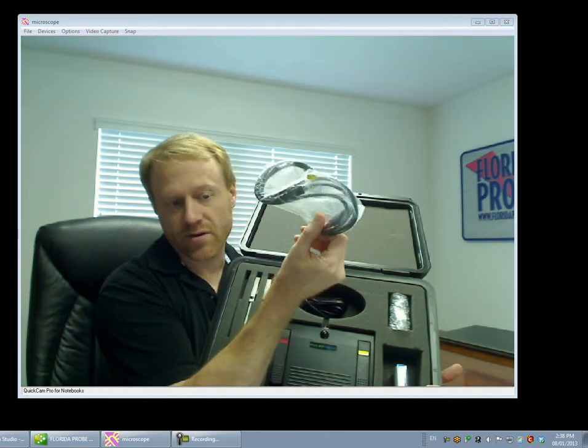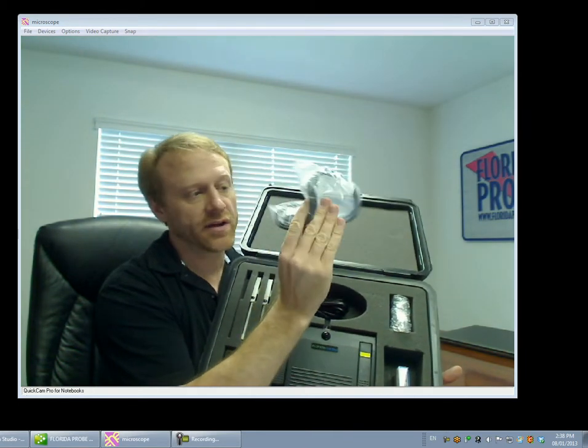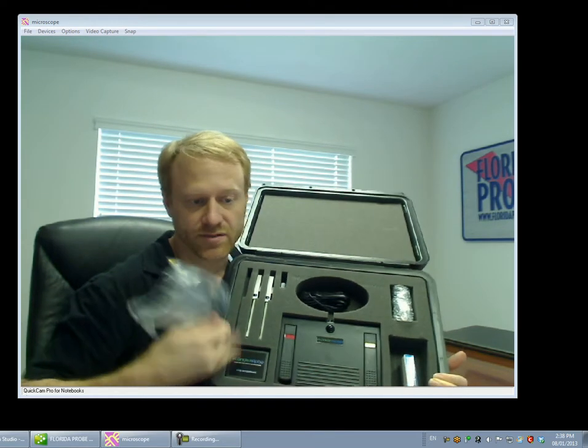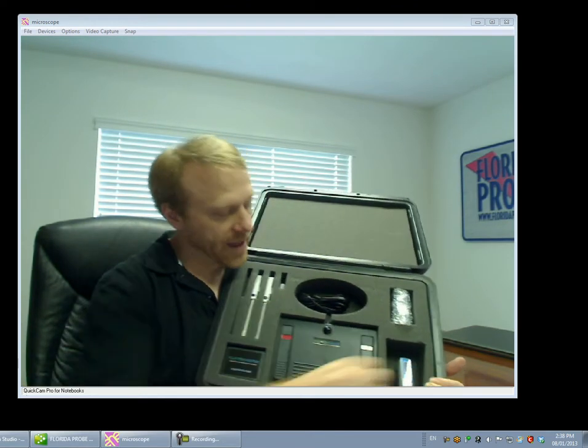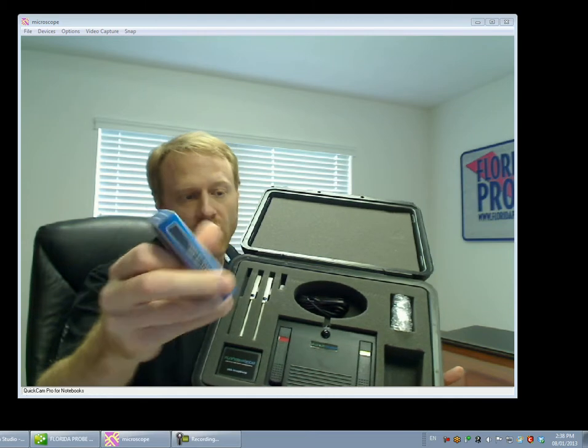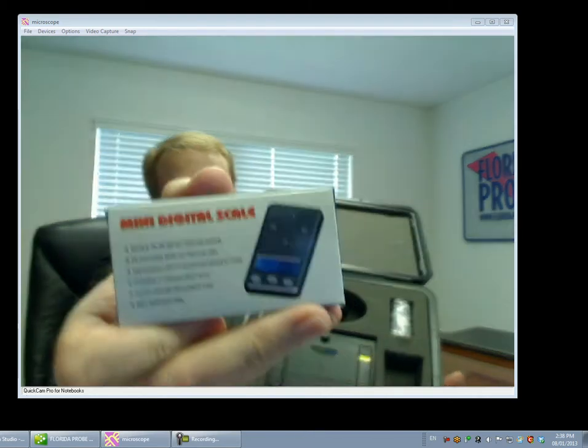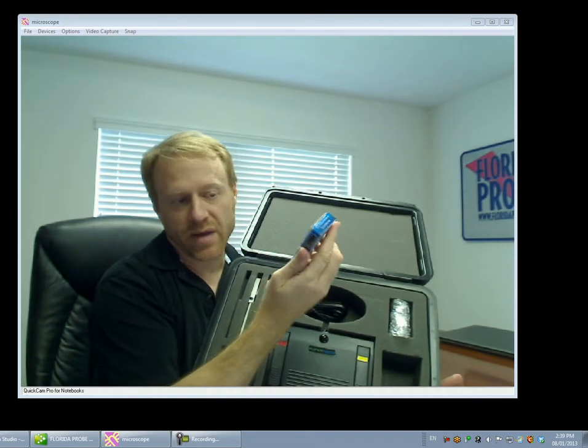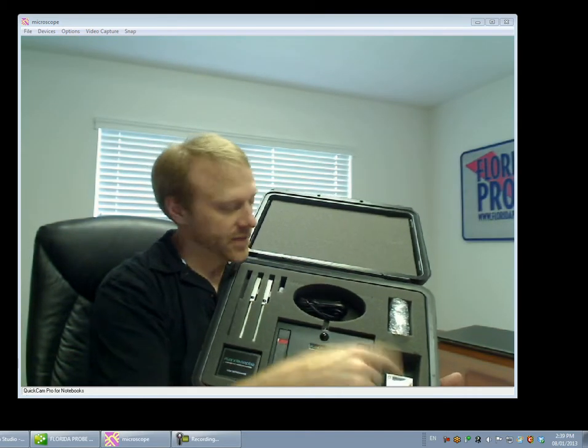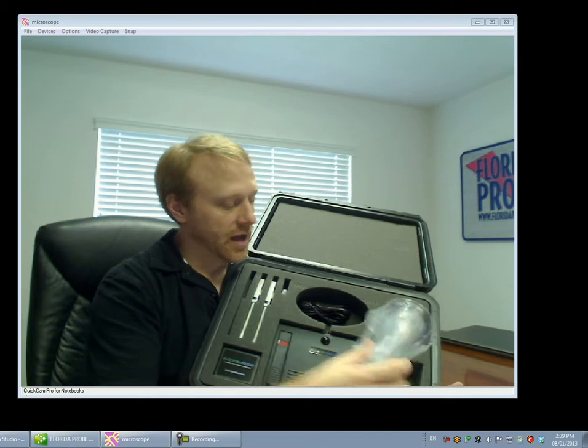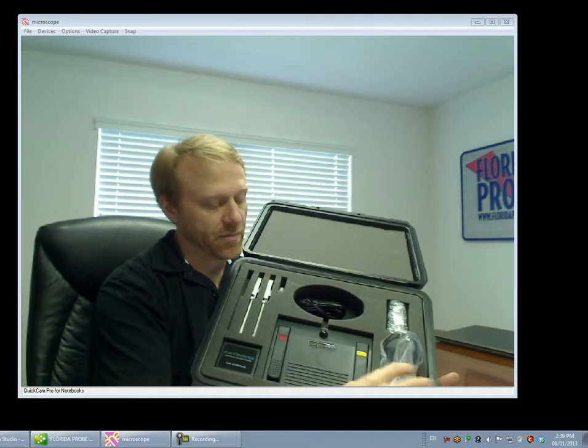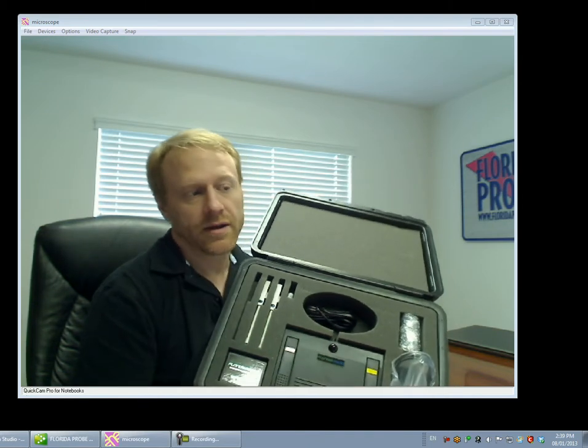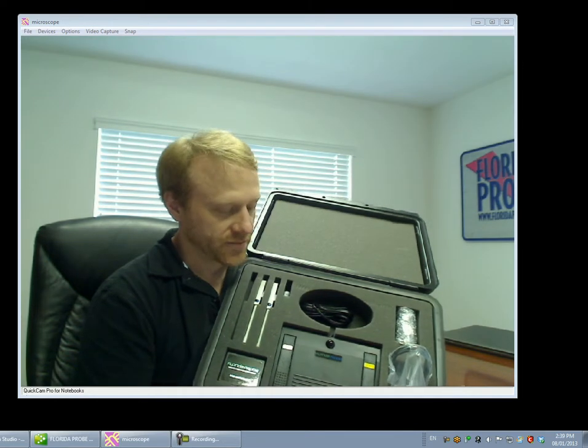Here's the actual cable. This is just a standard USB 6-foot black cable to be able to attach the USB device directly to your computer. And then here is also a gram scale. This is just a standard scale that measures force, and it will be used to calibrate and confirm that your encoder, months or years after the purchase, is still reading at the 20-gram force that it was designed for.